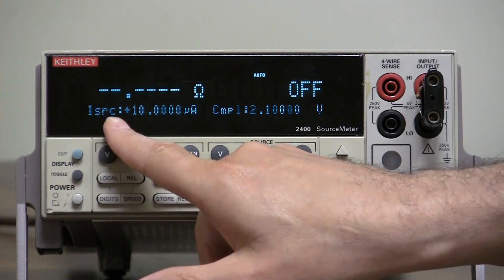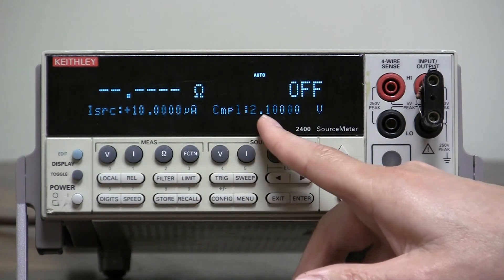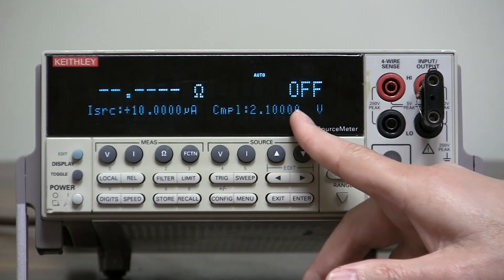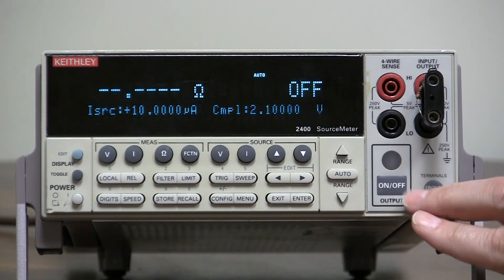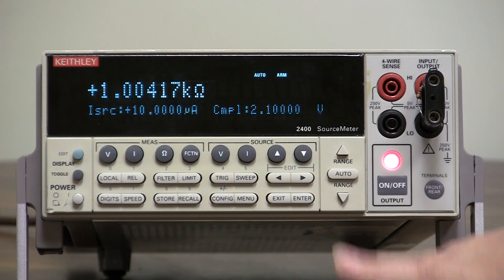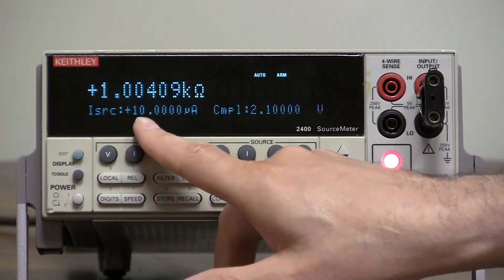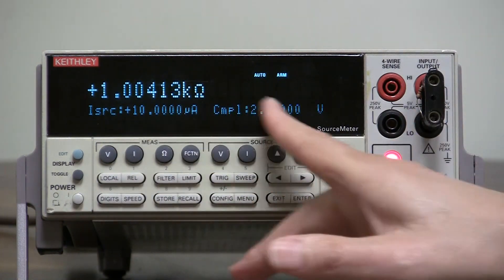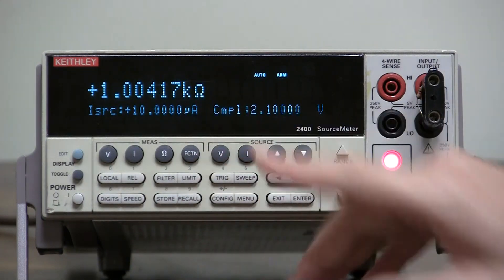Now, it automatically comes up with 10 microamps and compliance of 2.1 volts. Well, let's just see if that works. There we go, it's a 1K resistor, it's sourcing 10 microamps up to 2.1 volts for reading 1K ohms. Great.